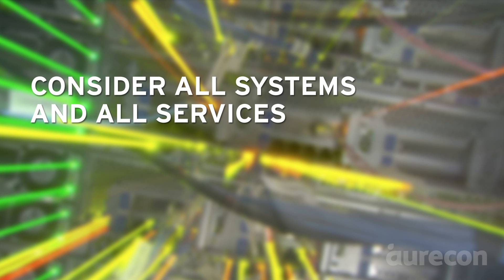Consider all systems and all services — it doesn't just apply to the electrical systems. It also applies across all of the services and infrastructure. Make sure you have enough capacity across all your mechanical systems, your fire systems, and also your hydraulics and plant, fuel storage, and various other things. Everything is affected by this need to make it modular and expandable as and when you need to grow.